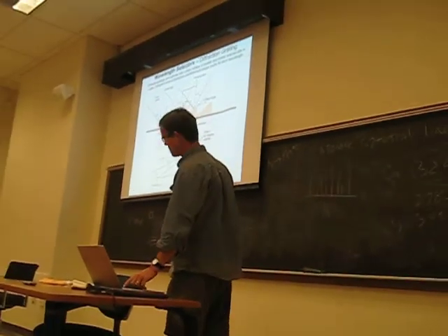And so in your instrument, when you dial in 324.8 nanometers, this is what the instrument's doing. It's rotating that grating so that it knows what to do in order to push the 324.8 nanometer wavelength through that slit. Okay. And this slit's relatively narrow, and the grating is quite sophisticated on these instruments compared to UV-vis, in terms of how finely graded they are, because they have to separate wavelengths that are much more discrete and defined. But they do a pretty good job of that.